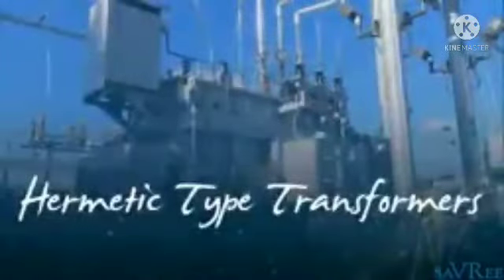The dry type transformer that we're looking at now is the simplest of the three that we're going to look at. And this dry type transformer consists of only the core, windings, and some cooling fans on the bottom. Let's now have a look at a hermetic type transformer. So here we are, we're now looking at a hermetic liquid immersed transformer. Let's have a spin.